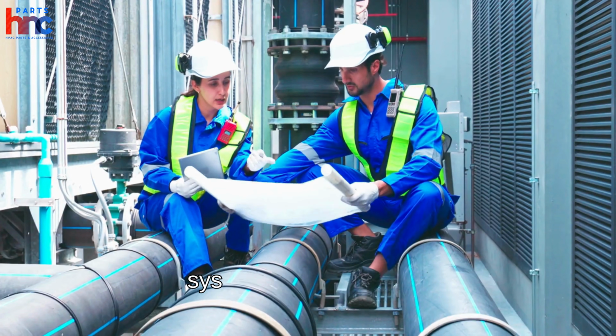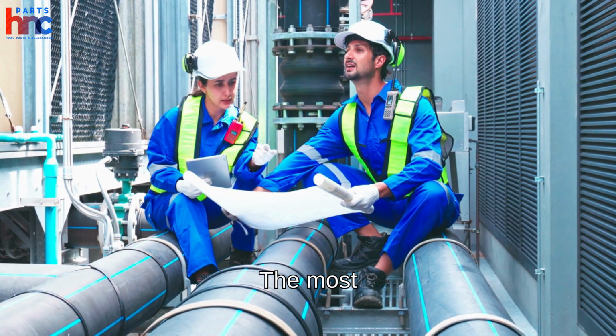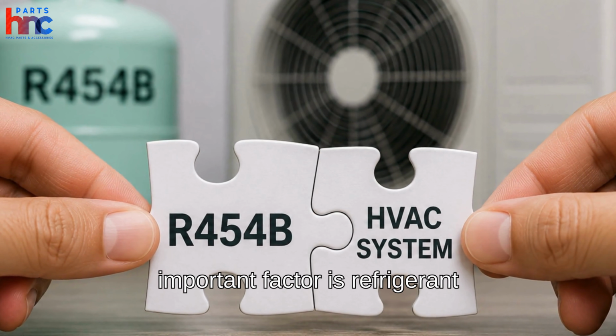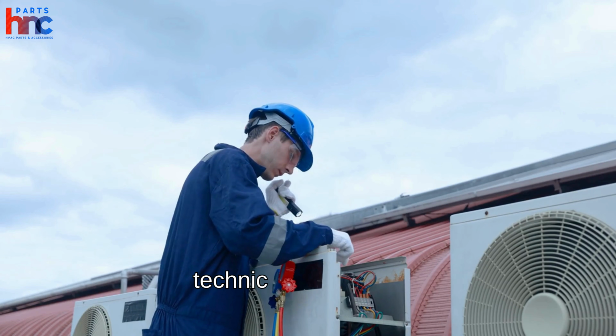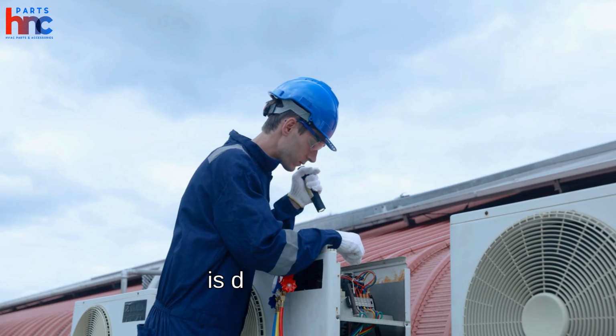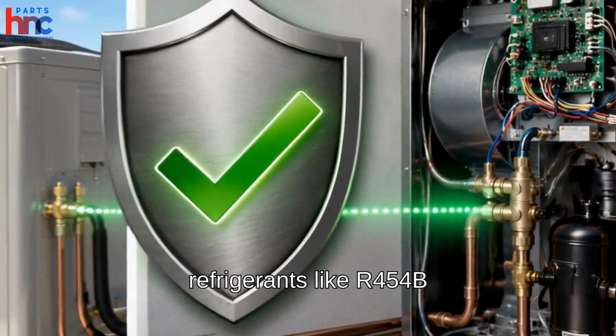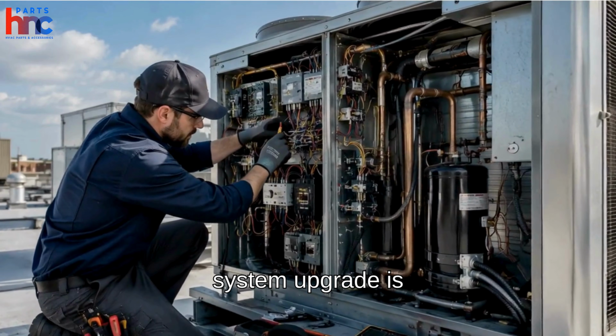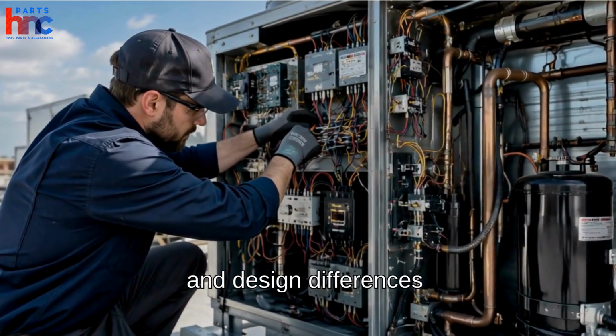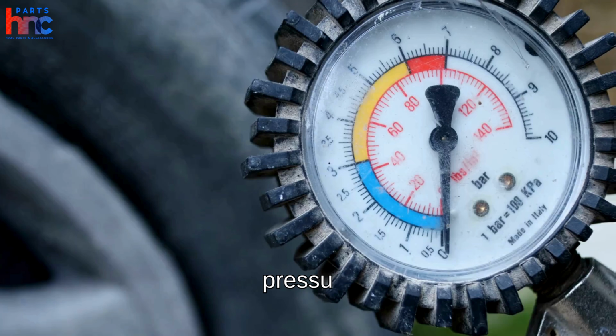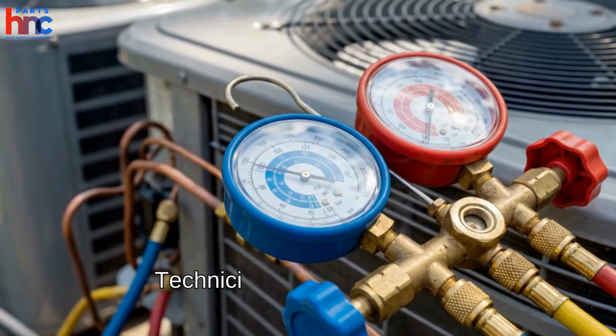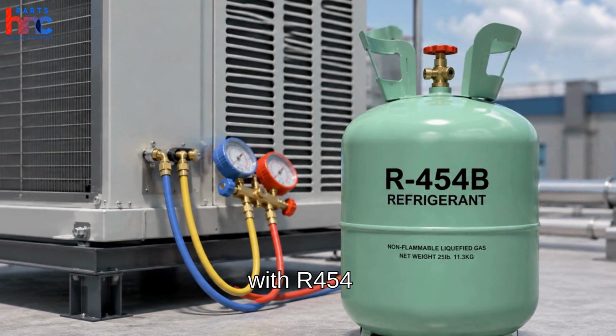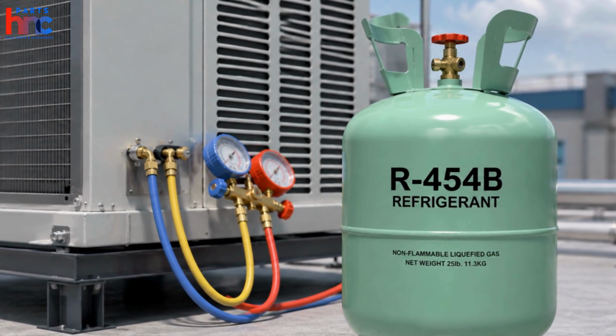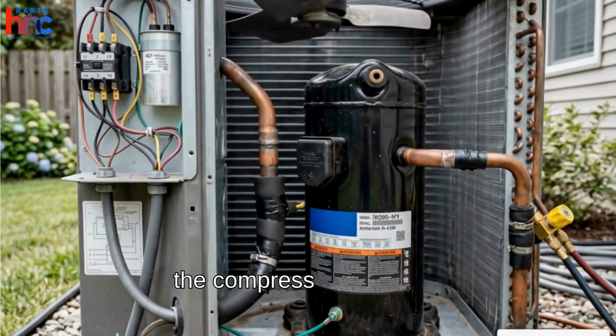Let's break down what really drives this refrigerant transition and how HVAC systems are evaluated during the upgrade process. The most important factor is refrigerant compatibility. To handle this, technicians first check whether the existing system is designed for A2L refrigerants like R-454B or if a full system upgrade is required due to pressure and design differences. If the system is compatible, pressure levels are carefully evaluated. Technicians inspect high side and low side pressures to ensure the system can safely operate with R-454B without stress or imbalance. Another key step is the compressor condition.